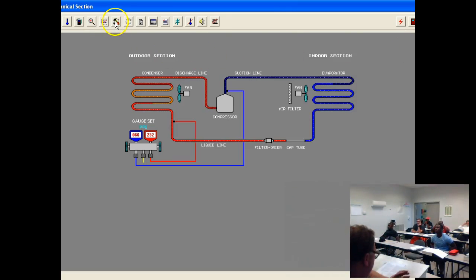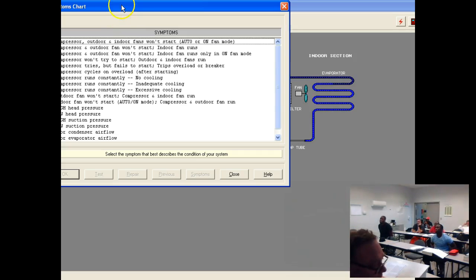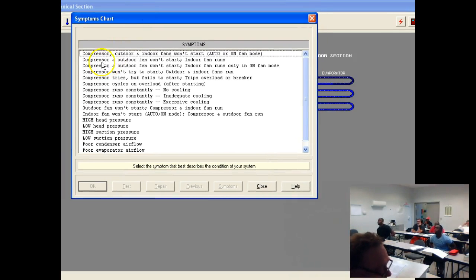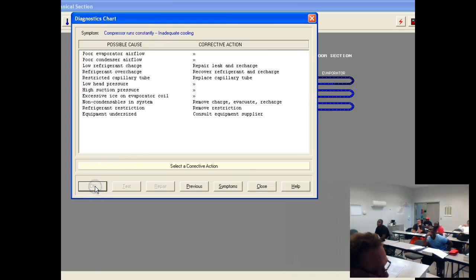I go to the hammer, screwdriver, wrench, and here are my symptoms. Compressor won't run, all that kind of stuff. I know I got low head pressure. I can select that. But I'm going to see if I got something else. That goes, compressor runs constantly, inadequate cooling. So I'm going to select that one. Okay. Now it's giving me 1, 2, 3, 4, 5, 6, 7, 8, 9, about 9 or 10. Poor evaporator airflow, poor condenser airflow. Anyway, you can start at the top.